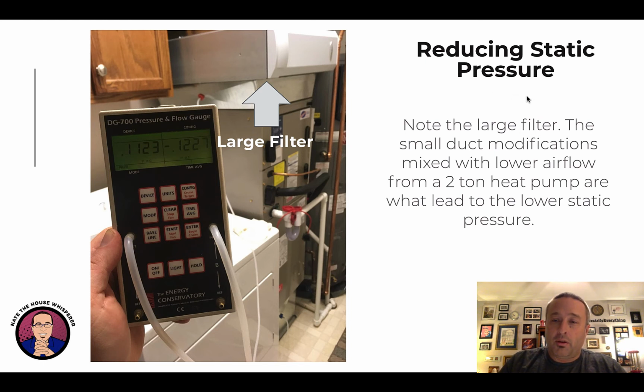But the duct modifications that happened here, pretty small duct modifications, mixed with the lower airflow from a small heat pump that is right sized to the house, and we did some air sealing on this house as well - relatively minor. I think we got a 20 or 25% drop, and most of my drops are upwards of 50%. But by running this nice big filter, which has very low pressure going across it, and running a nice large duct and downsizing the unit, we didn't change anything else in this house. One small addition, there's a little duct behind here going to the bedroom behind this space. But this led to about a 2/3 drop in static pressure with the same duct system.